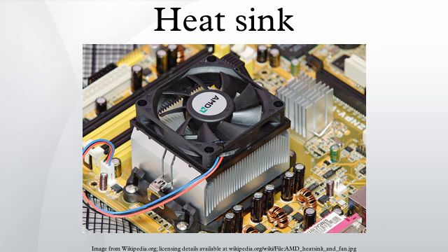Experimental methods. Experimental tests are one of the more popular ways to determine the heat sink thermal performance. In order to determine the heat sink thermal resistance, the flow rate, input power, inlet air temperature and heat sink base temperature need to be known. Figure 2 shows a test setup for a ducted flow heat sink application. Vendor-supplied data is commonly provided for ducted test results. However, the results are optimistic and can give misleading data when heat sinks are used in an unducted application. More details on heat sink testing methods and common oversights can be found in Azar et al.